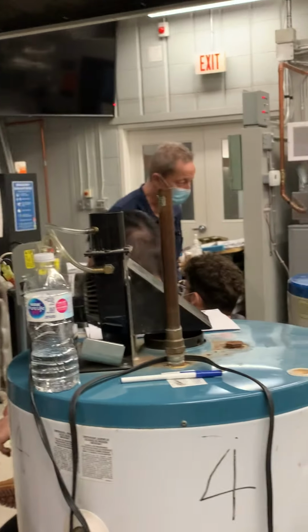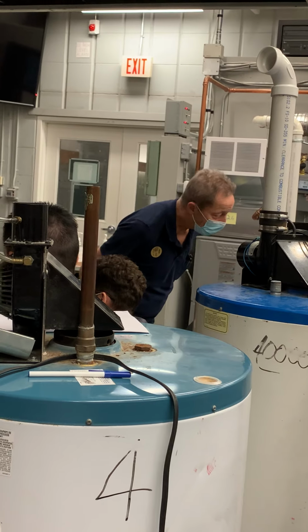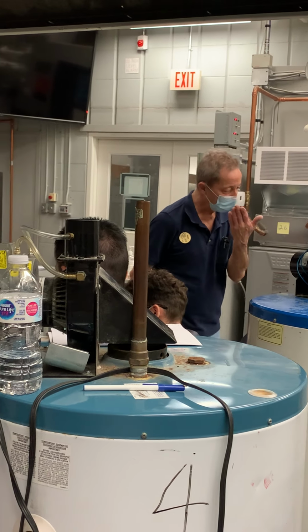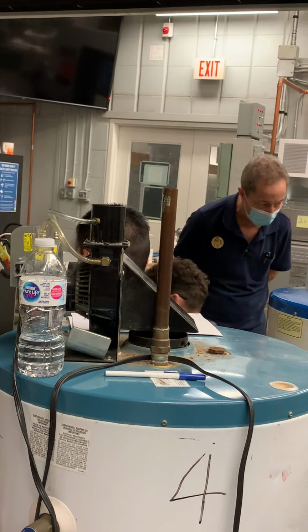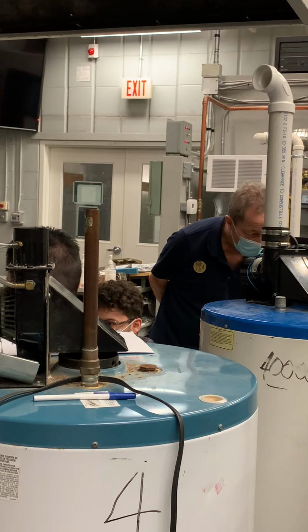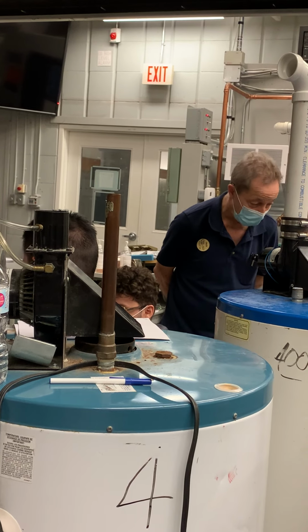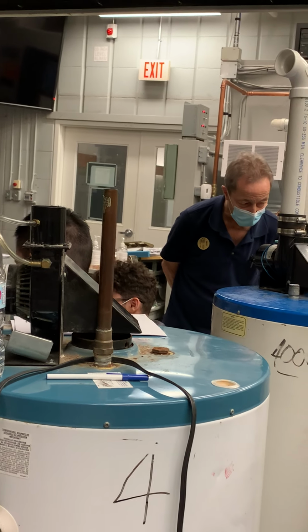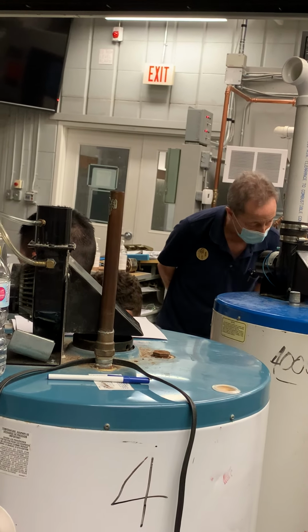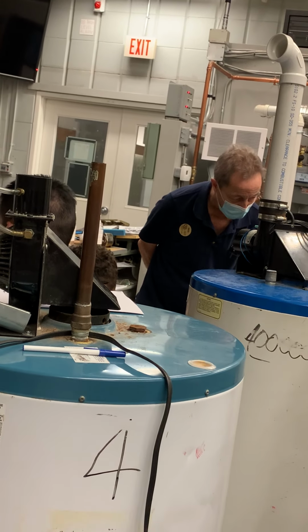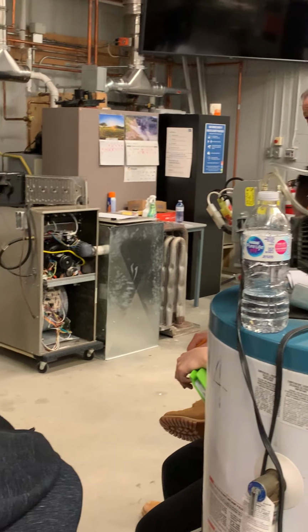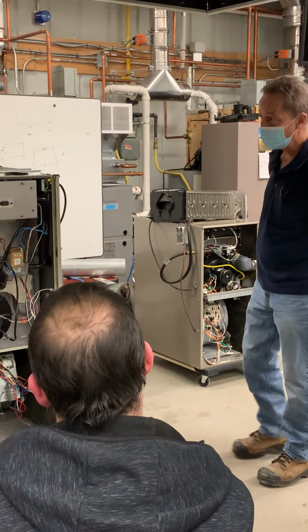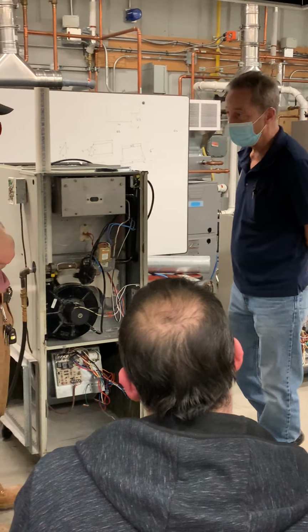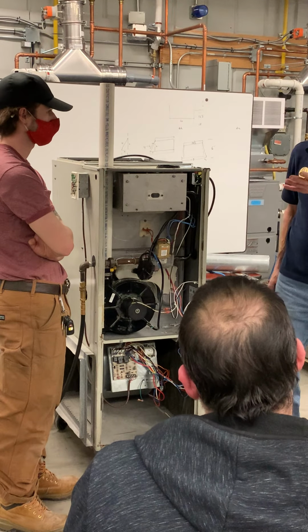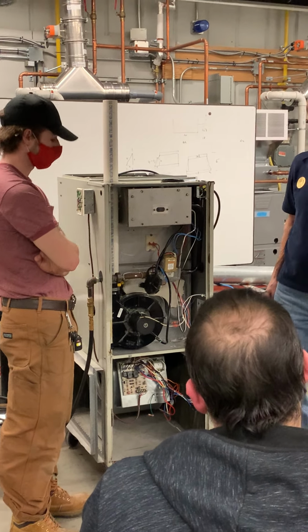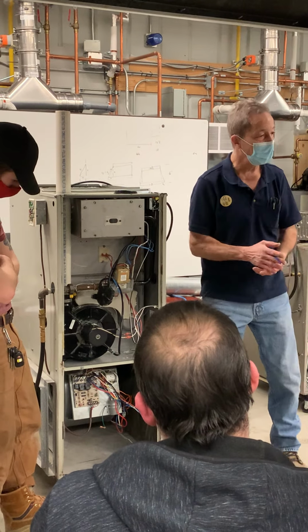What happens in the secondary heat exchanger? Okay, so air from the house will pass over the secondary heat exchanger. What happens inside the secondary heat exchanger? Heats up the air. No, inside. Outside, it heats up the air. Inside the secondary heat exchanger, what happens? What's going through the secondary heat exchanger? Inside it. Flue gas? Flue gases. So what happens to the flue gases? Condense? They condense. And what happens when you condense? You get water? And you get extra energy out of the flue gases, right? Because as I'm changing from steam or humidity into water, I get extra energy out of it. So that's how it turns into a high efficiency.